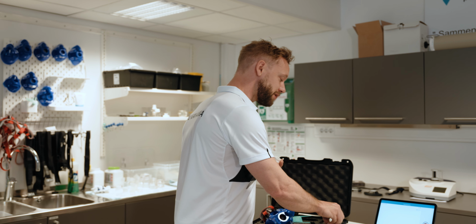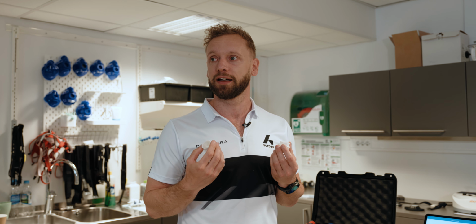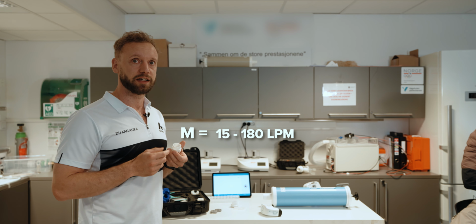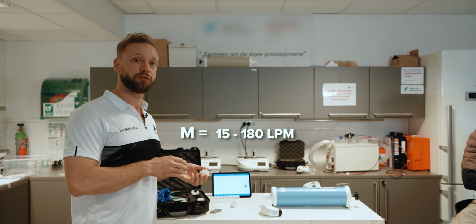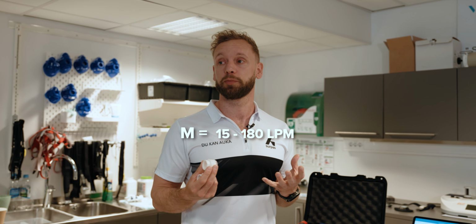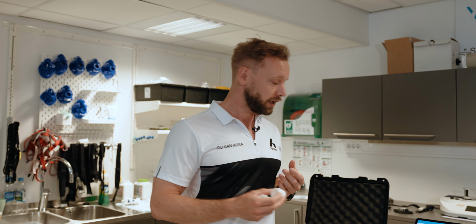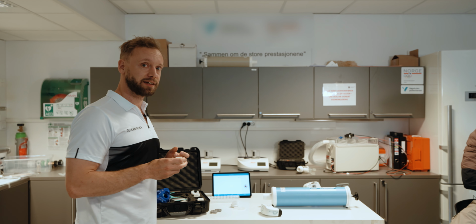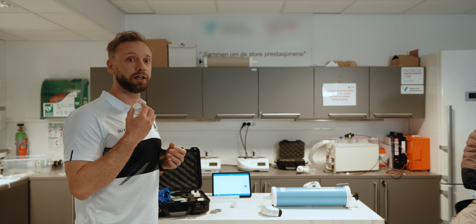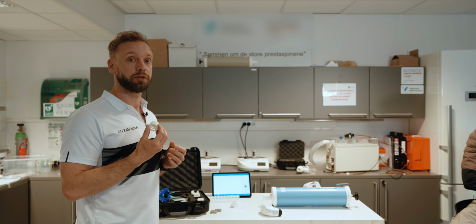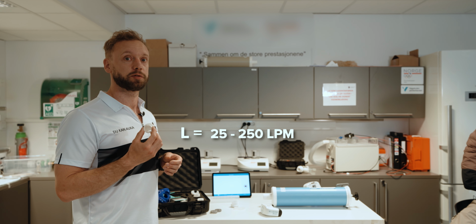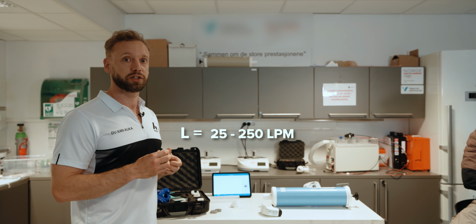Then you have the 2 sizes that you use when you test a person working. The medium size is for ventilation of 15 to 180 liters per minute. That user piece will fit most people. If you are working with elite athletes, you should consider choosing the large user piece. That will overlap the medium user piece by quite a bit. It starts at 25 as opposed to 15 liters per minute, but it will go all the way up to 250 liters per minute, which is quite a large ventilation.